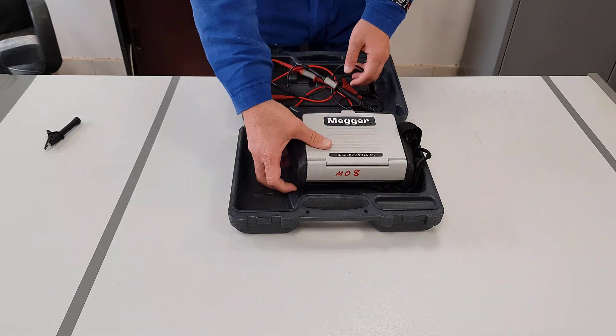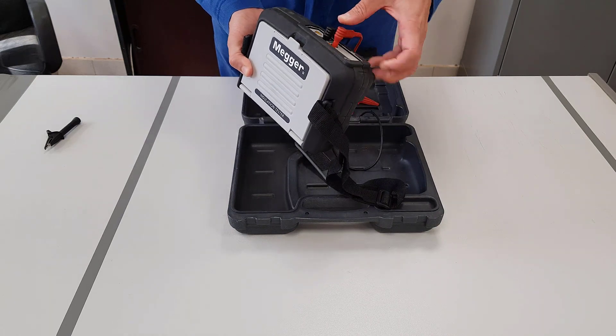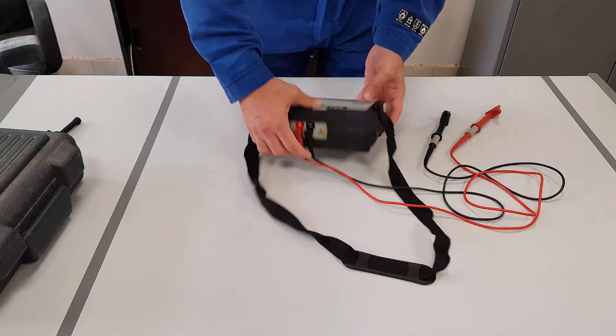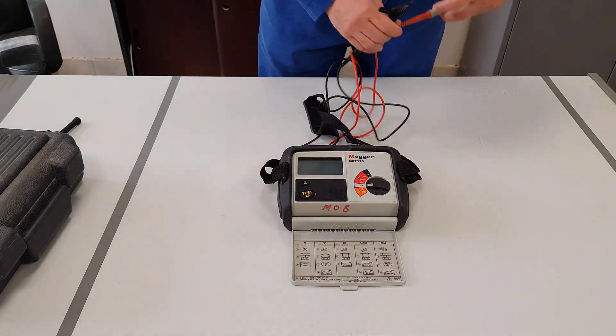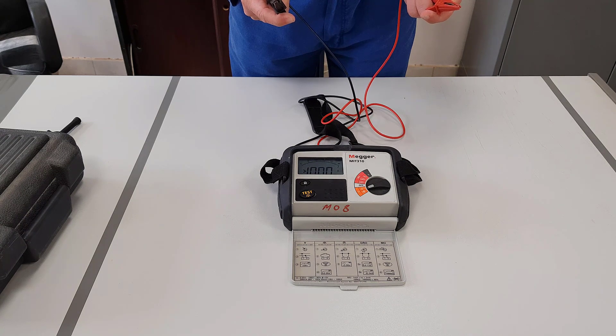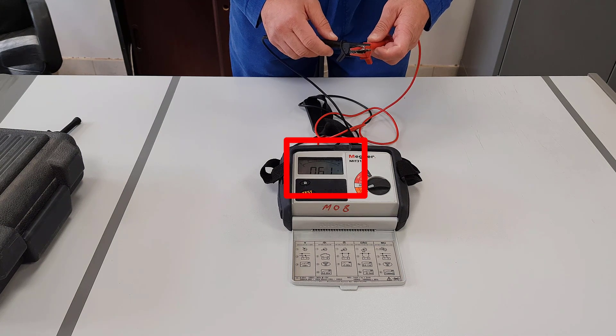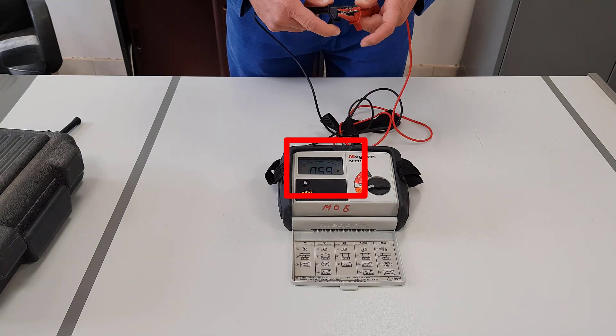Now we're going to put the leads into the meter. The black one goes into the black connection and the red one goes into the red connection. Now we're going to rotate the selector switch to the ohms position. As you can see, the meter goes to 1000 ohms. The scale goes to the right-hand side to show that there is infinite resistance between the probes. If you connect the two probes together, you'll see the meter goes down and we now have a reading of 0.61 ohms. This value has to be remembered because it will have to be subtracted from any resistance value that we then take.